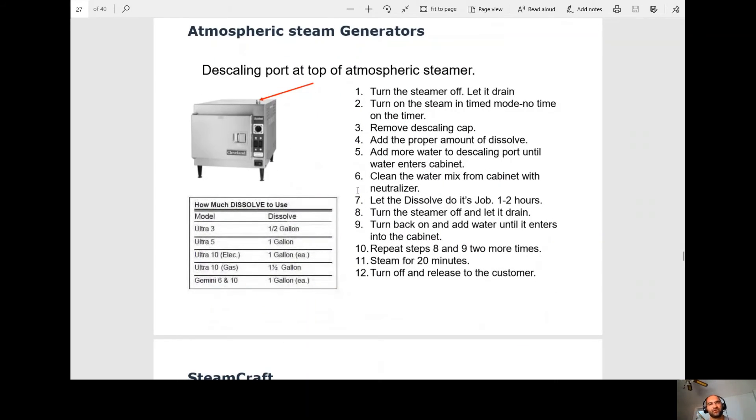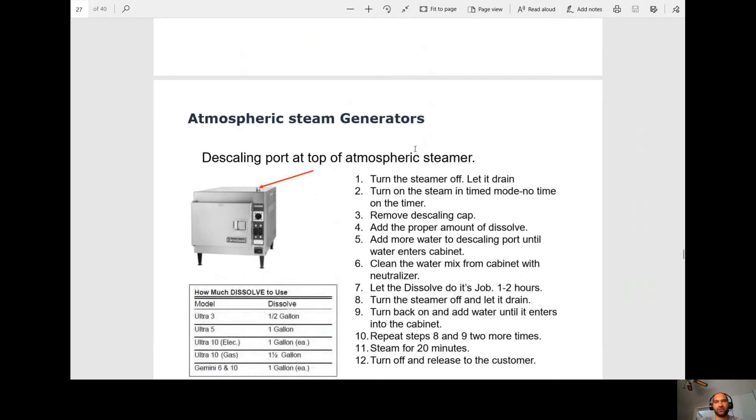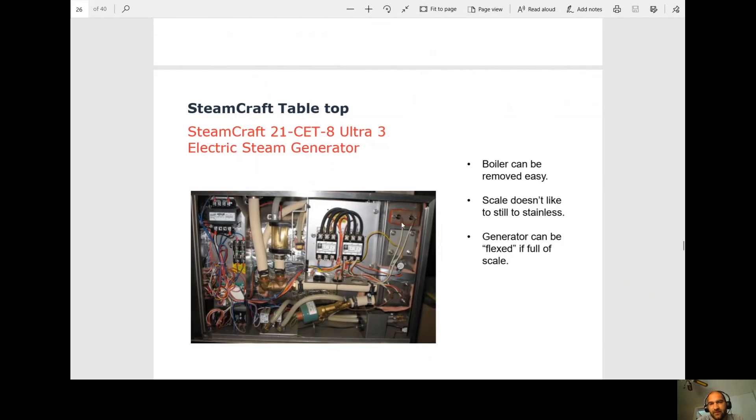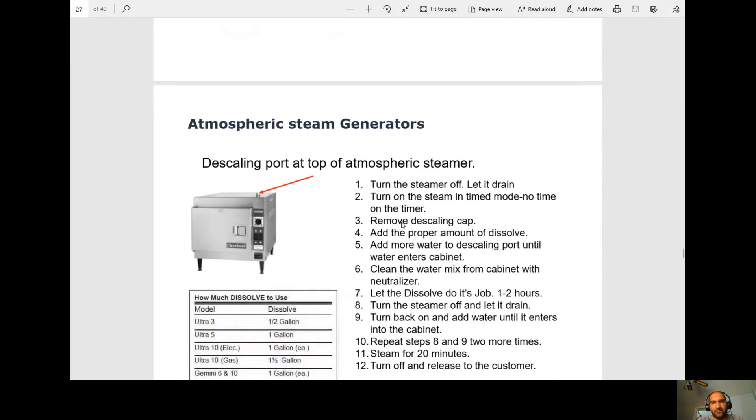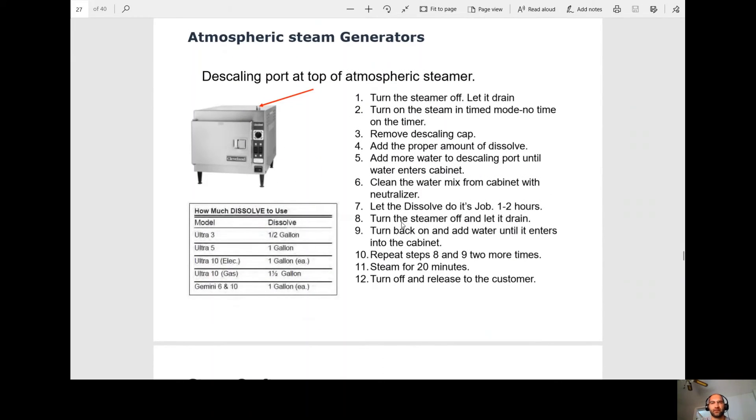So this is the procedure for descaling. Turn the steamer off, let it drain, turn on the steam and time mode and put no time on the timer. So why we do that? We don't want the unit to heat. So there will still be some heat. If we look here, there's a preheat element. We're going to have minimal heat from that. So it's important that we do this when we're not heating. Remove the descale cap. Add the proper amount of dissolve. Add more water to the descale port until water enters the cabinet. So you'll open the door. You'll see it overflowing from the boiler into the cabinet. Now we know we're full. You want to clean that water mix that's spilt into the cabinet with a neutralizer.